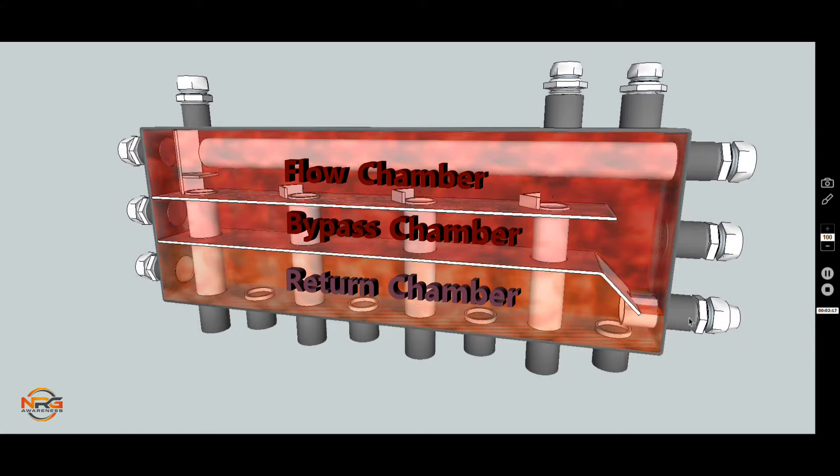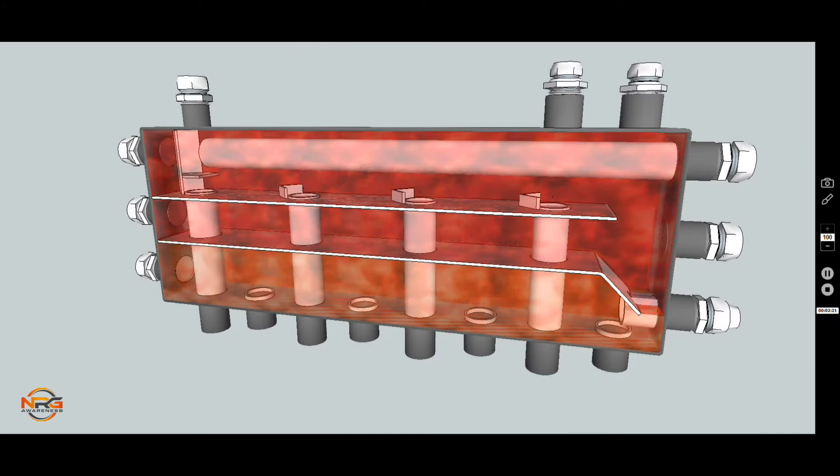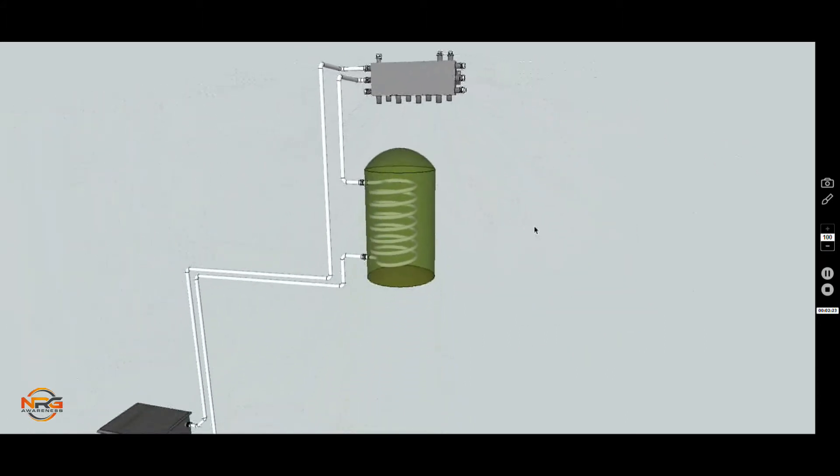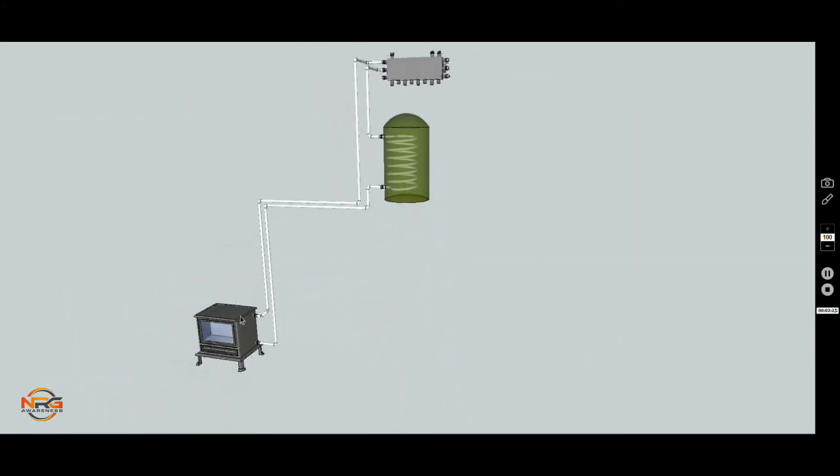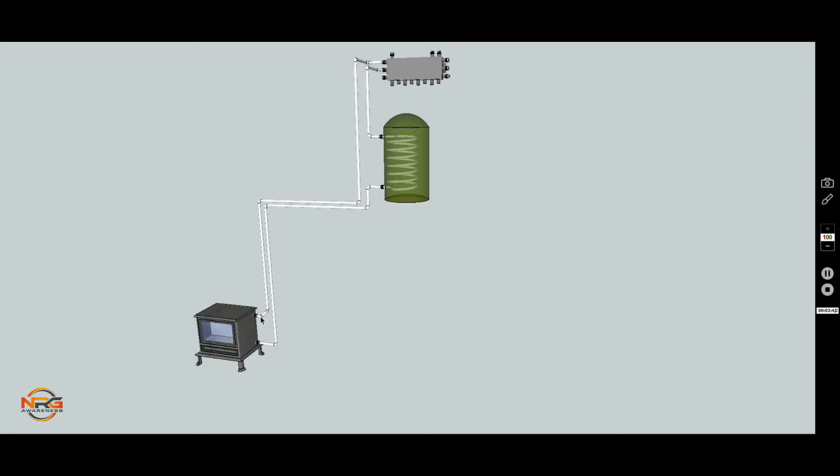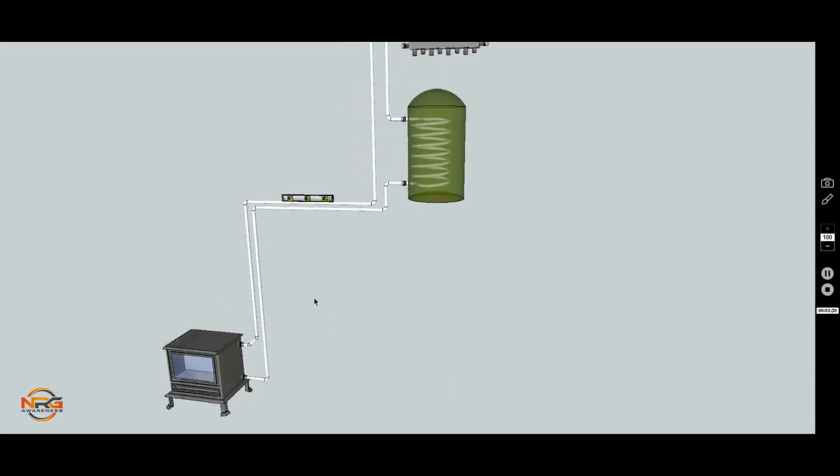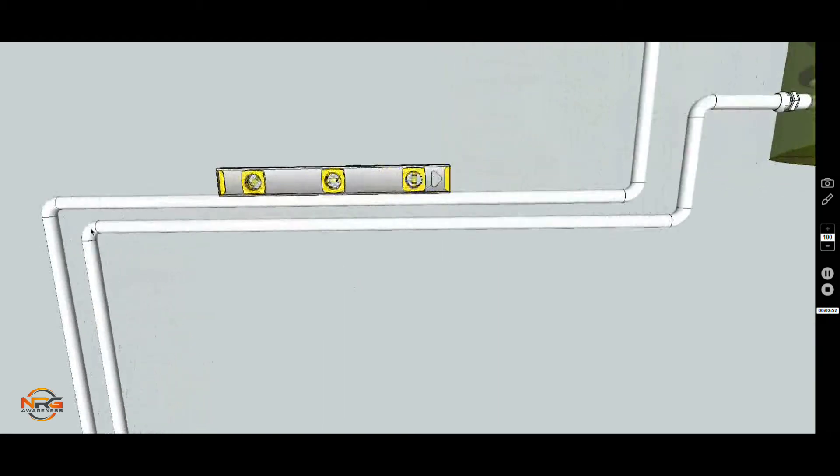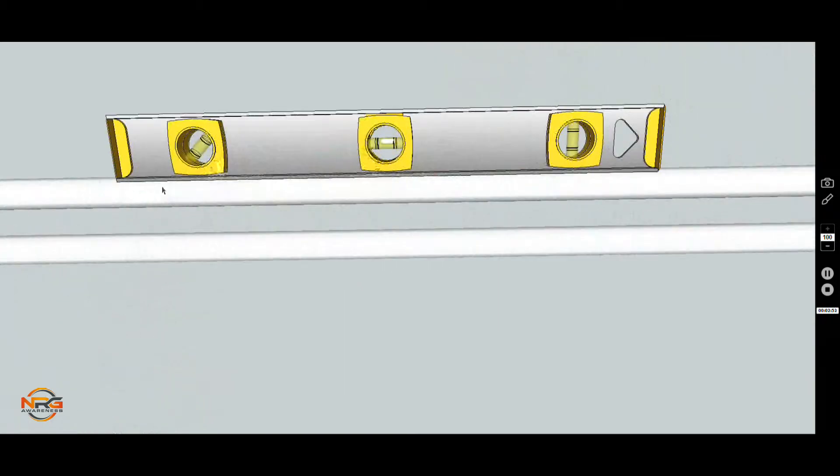If we introduce a stove on the left hand side, you can see by taking a vertical rising flow pipe from the top of the stove, being pushed as quickly as possible into a vertical position, and then rising from across any horizontal runs, again to rise up into the Energy Zone. It's very important that you cause a vertical rise as quickly as possible with any stove, and it's also very important that any horizontal pipework would rise across towards the high point being the Energy Zone unit. It's necessary to make sure this rise is maximized. This applies to the flow and to the return pipe from the stove.